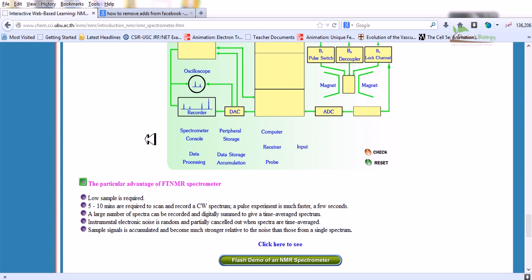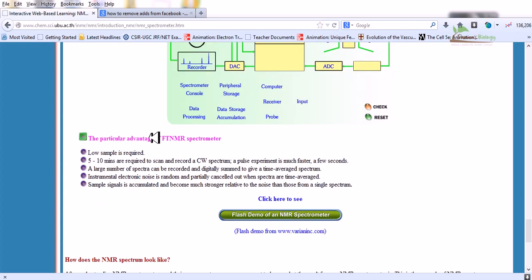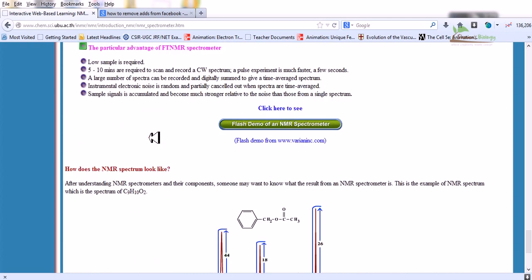The particular advantage of FTNMR spectrometer is that low sample is required. Second, 5 to 10 minutes are required to scan and record in traditional spectrophotometry, but a pulse experiment is much faster, just a few seconds. A large number of spectra can be recorded and digitally summed to give an average spectrum. Instrumental electronic noise is random and partially cancelled out with modern technologies. The sample signal is accumulated and becomes much stronger relative to the noise than a single spectrum.